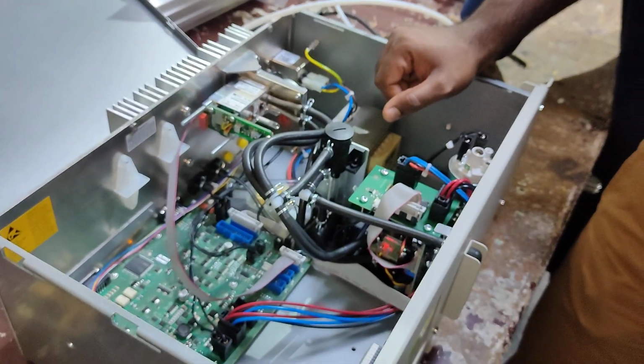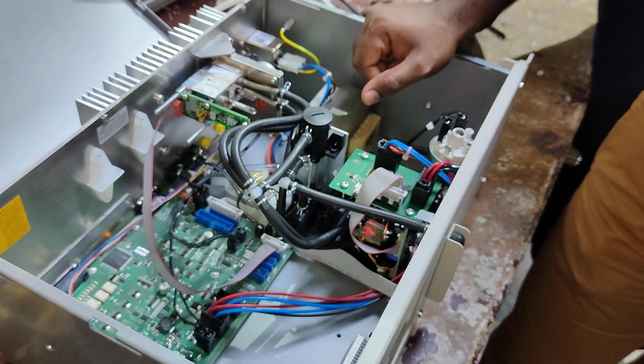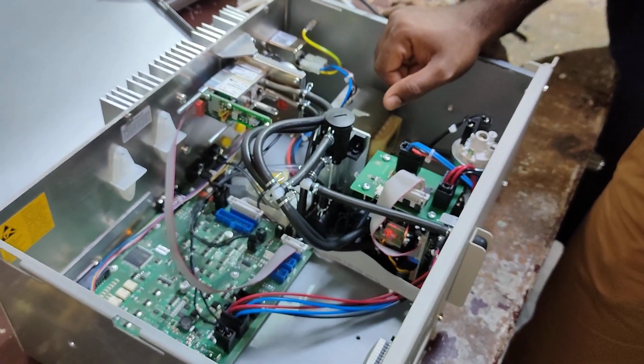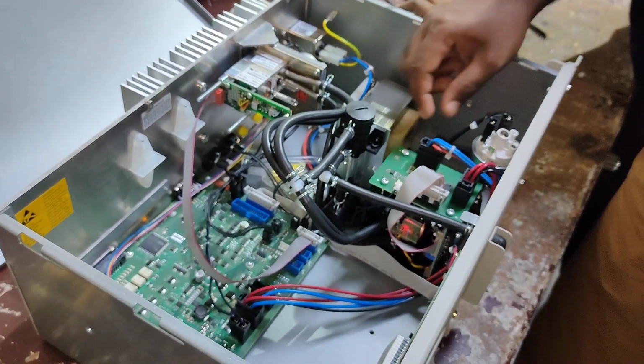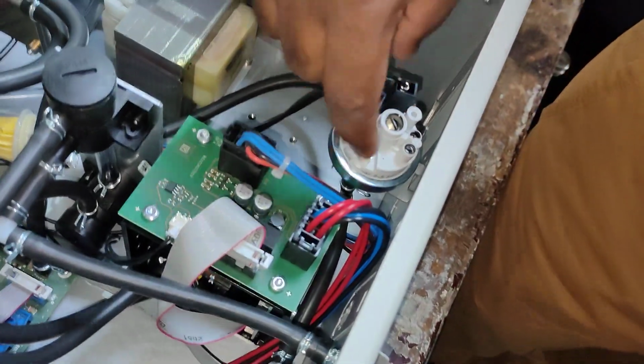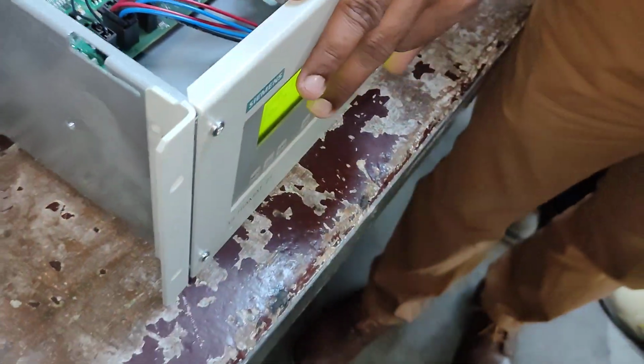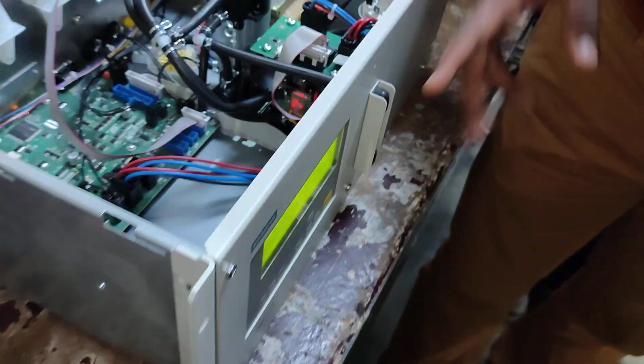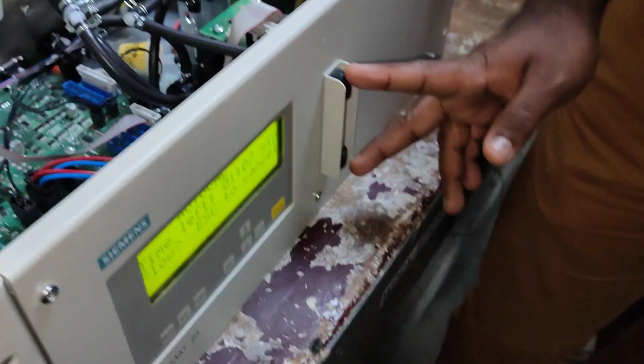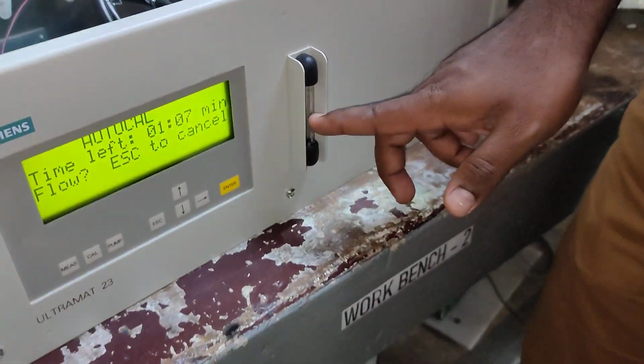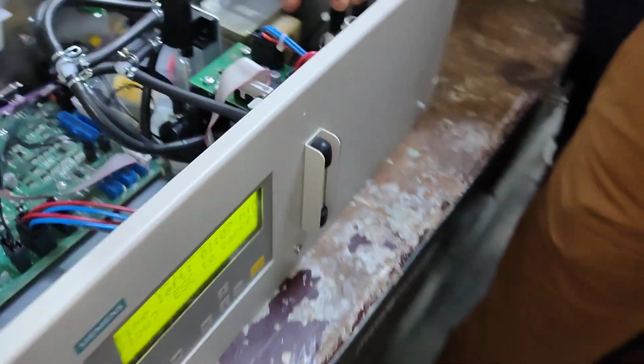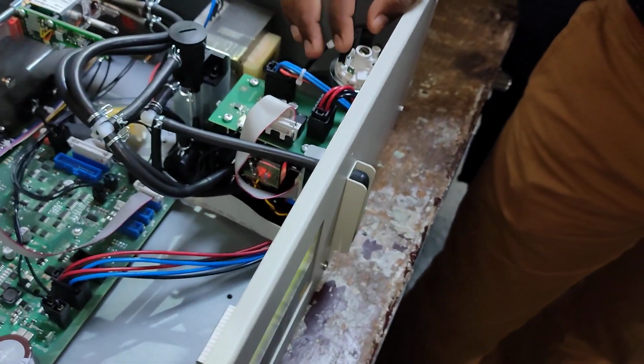We don't have any spare for individual parts. Is a part number available for the full unit? Yes, it is available. And what is that? That is the pressure switch. This is a switch which tells whether there is a sample or not during autocal. This switch is connected across the flow meter. So if you have 50% of the flow here, then this switch will close.